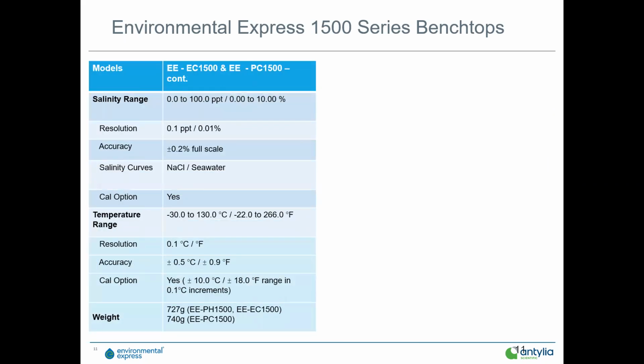And then finally, salinity range, excellent, 0 to 100 parts per thousand, good resolution, great accuracy, 2 salinity curves, seawater or sodium chloride, calibration option on that as well. Temperature, again, the key feature here is it's got a good range and it's got that cal option on the temperature. Most temperature sensors used nowadays in electrochemistry, especially lab electrochemistry, are thermistors. They're very fast, they're very durable. There's little drift usually. So it's a pretty stable temperature element.